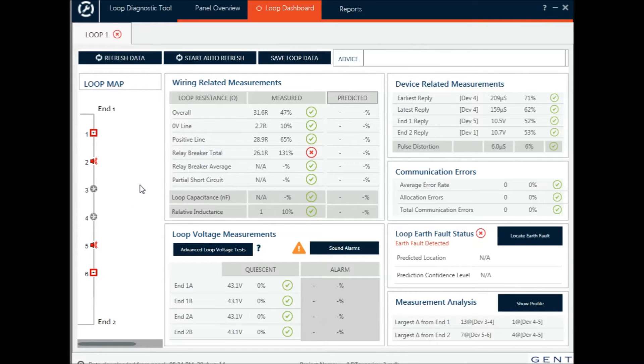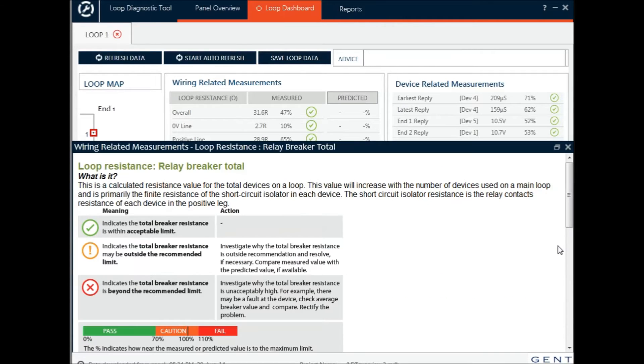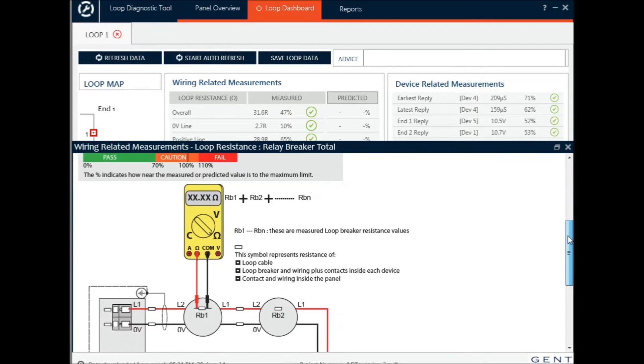On the loop map, at a quick glance I can tell from the green ticks and the red crosses that I've got a problem here with the relay breaker total and I've also got an earth fault detected. If I don't know what this means, I can click the red cross to bring up the context-sensitive help, which gives me all the information I might need to understand what the problem might be and tips on how to go about solving it.